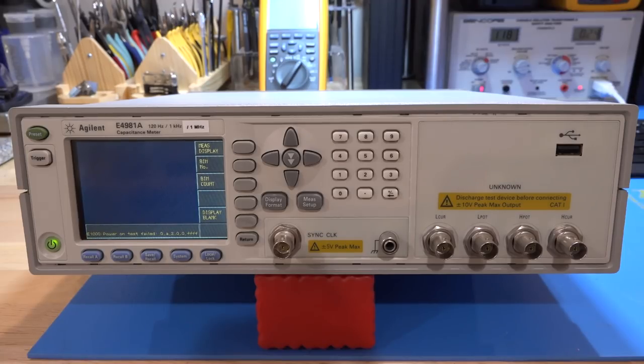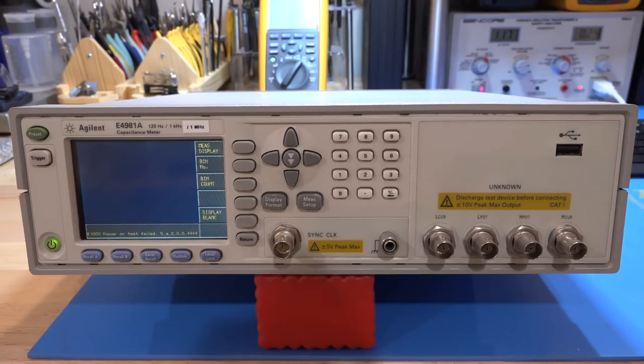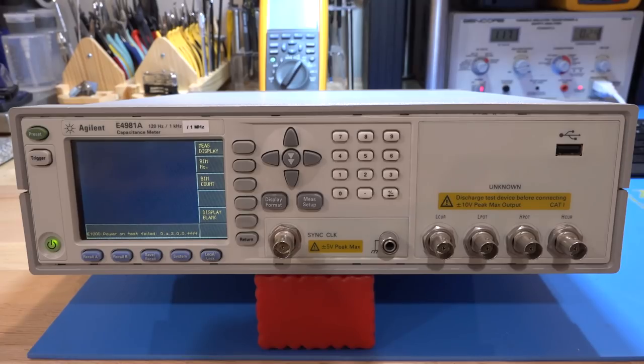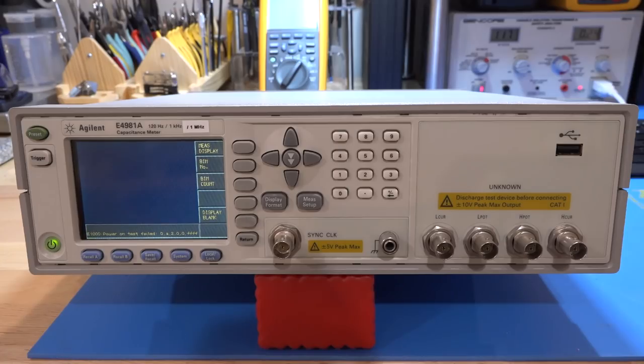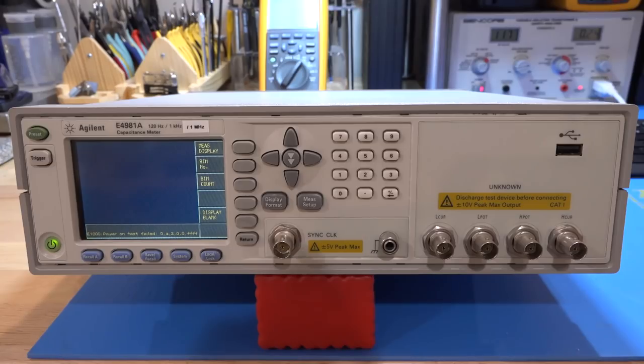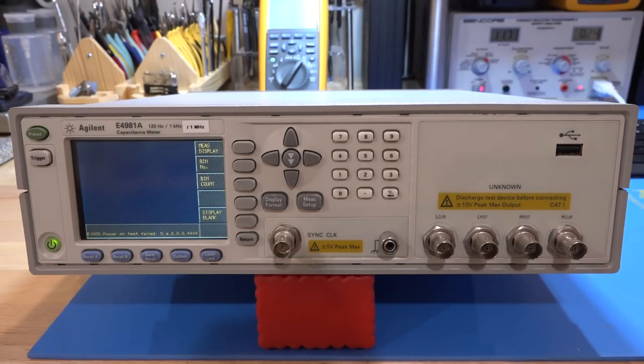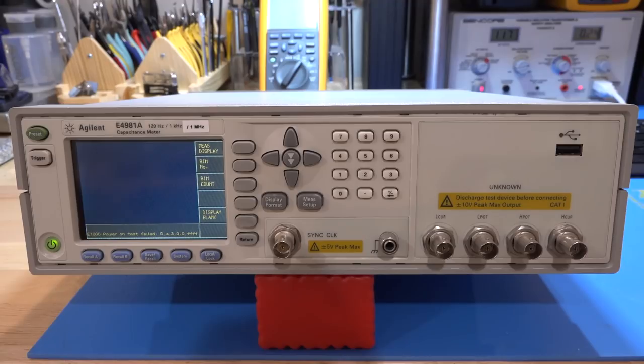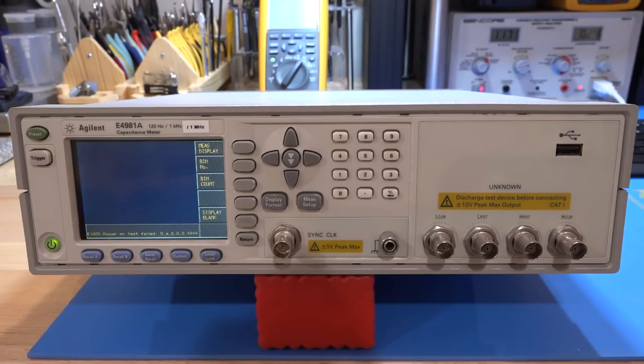It turns out these four Fs point to the CPU, some kind of a main processor board problem. So it doesn't boot up correctly. Now, maybe somebody tried to update the firmware, and that's what actually broke it. And that would explain why the firmware is the latest Keysight firmware. So either way, I think it's worthwhile to take a look. Now, I tried to communicate with it. It really doesn't do anything when it is stuck this way. Maybe there's a magical way of booting it up with holding some buttons, and then it will go into some safe boot mode. But anyway, couldn't find it on a quick glance. No matter what, we're going to take it apart anyway to take a look at it.